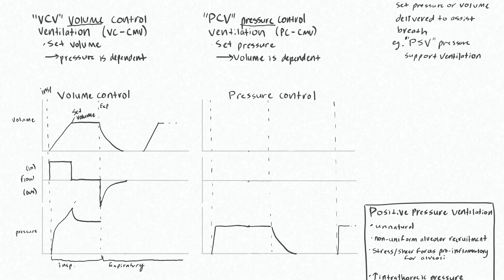Once you're at the maximum volume delivered, the flow is zero because you have nothing moving in or out until you reach your expiration phase — then you'll have negative flow leaving the patient, which eventually becomes zero again. The resulting airway pressure increases and you reach some peak pressure right at the end of when your flow stops or when you reach your maximum volume. During this inspiratory hold period, the pressure plateaus a little bit lower than your peak pressure.